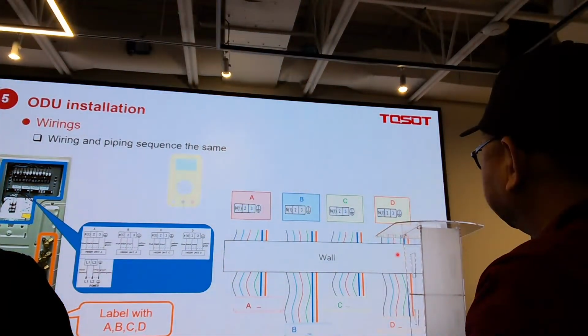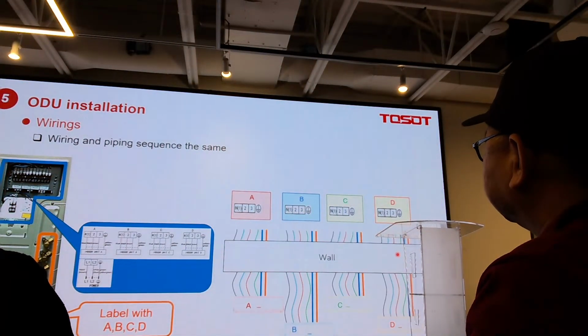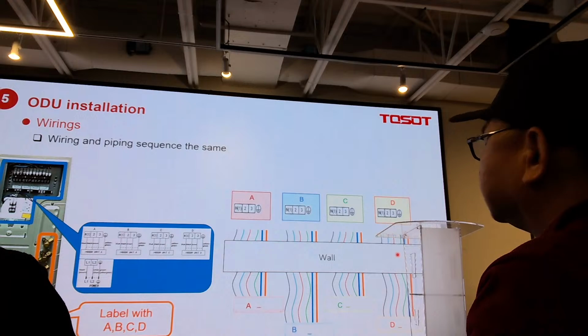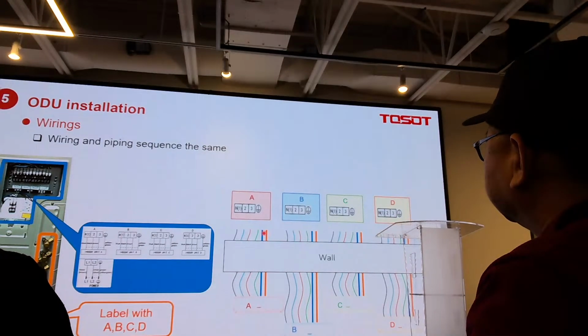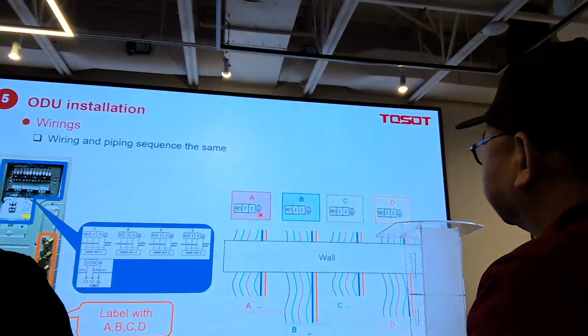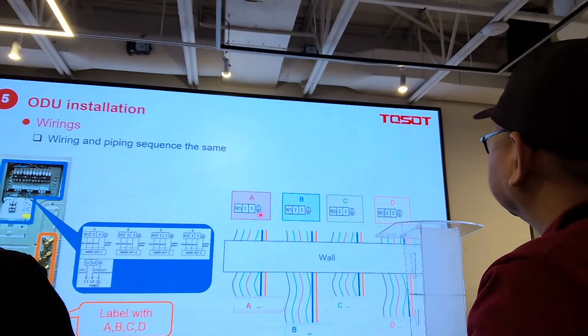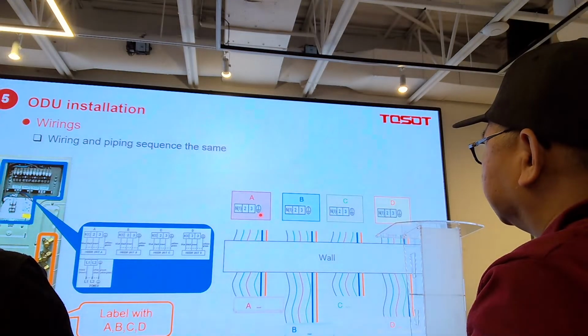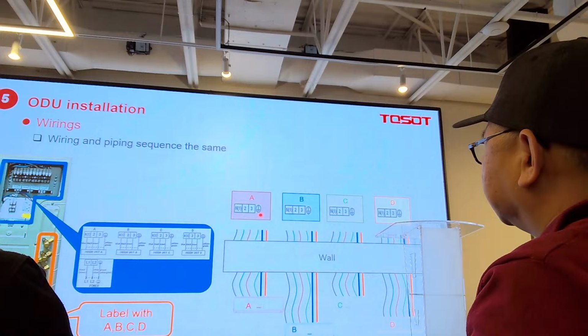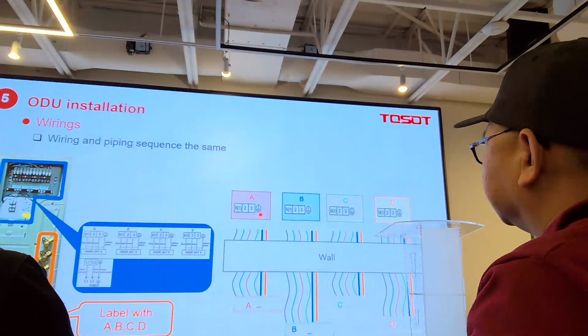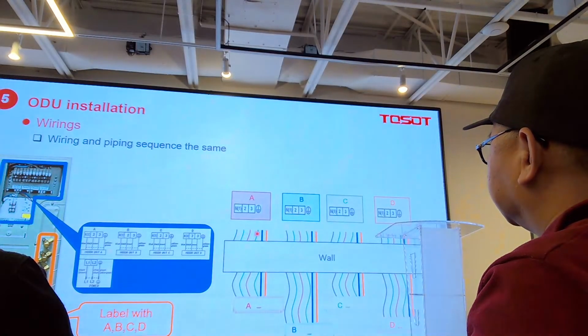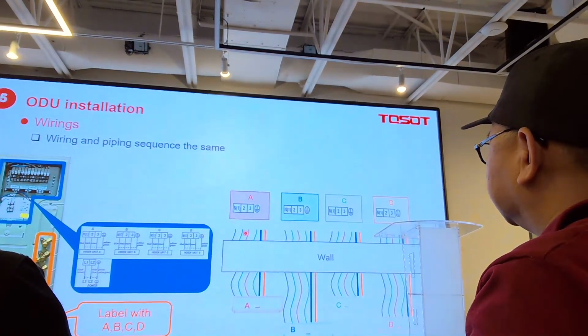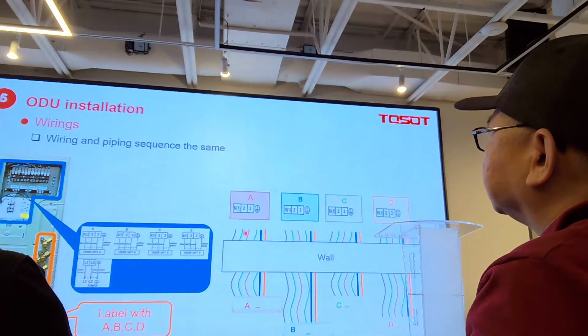And I need to ask you a question: when you pull out all the copper tubes and the wires to the outdoor unit, how can you identify them as belonging to the same indoor unit? Is there any method or know-how to identify them? Because you need to guarantee the sequence, right? When you pull out all the pipes and wires to the outdoor unit to do the wiring or the connected tube, how can you identify them from the same indoor unit?